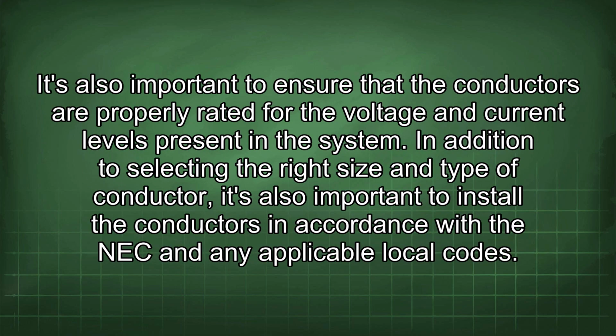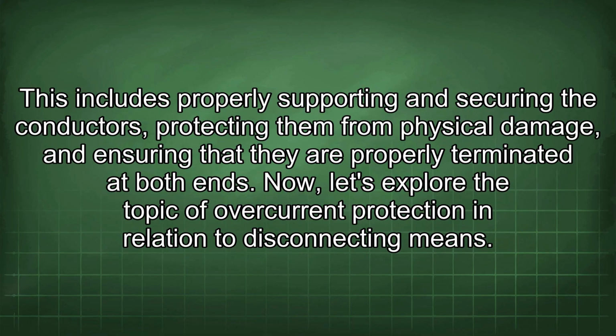It's also important to ensure that the conductors are properly rated for the voltage and current levels present in the system. In addition to selecting the right size and type of conductor, it's also important to install the conductors in accordance with the NEC and any applicable local codes. This includes properly supporting and securing the conductors, protecting them from physical damage, and ensuring that they are properly terminated at both ends. Now let's explore the topic of overcurrent protection in relation to disconnecting means.